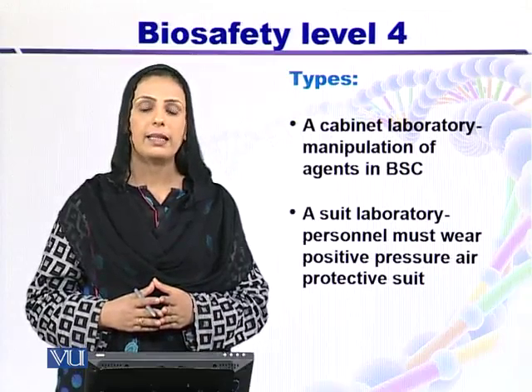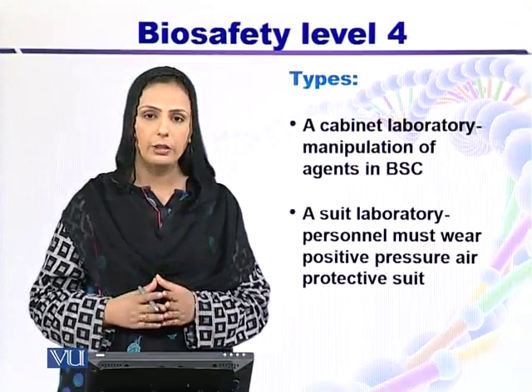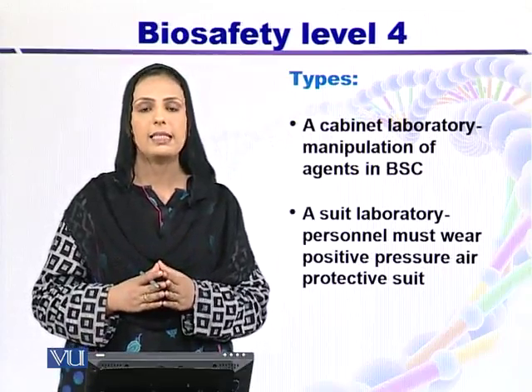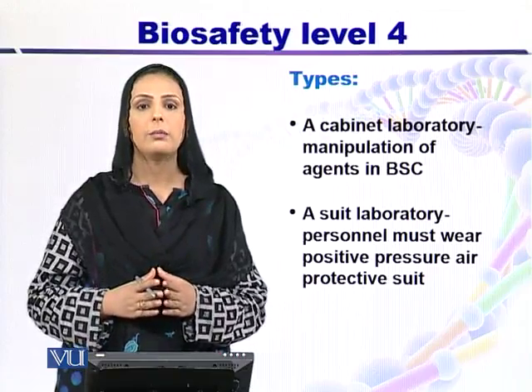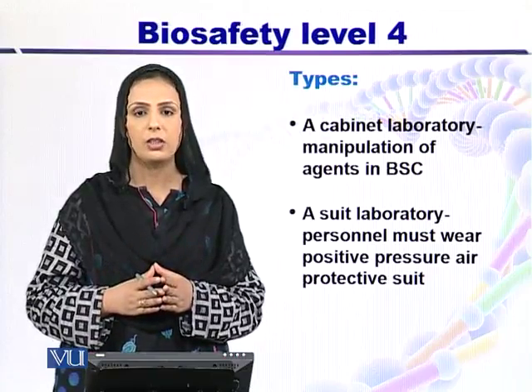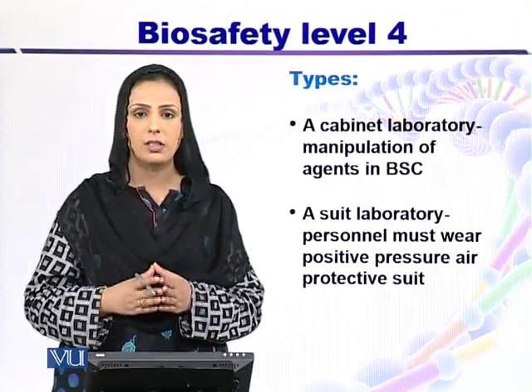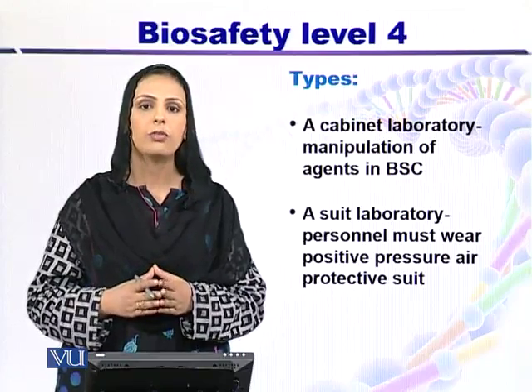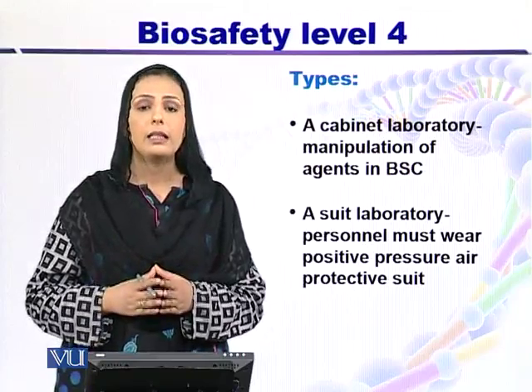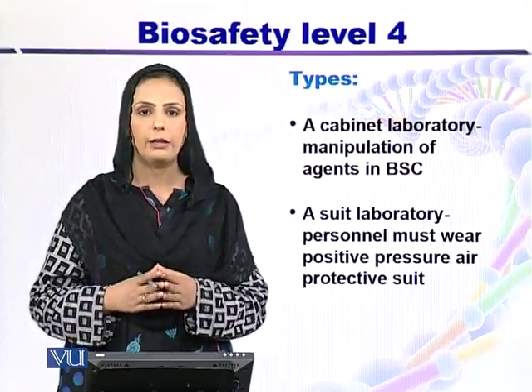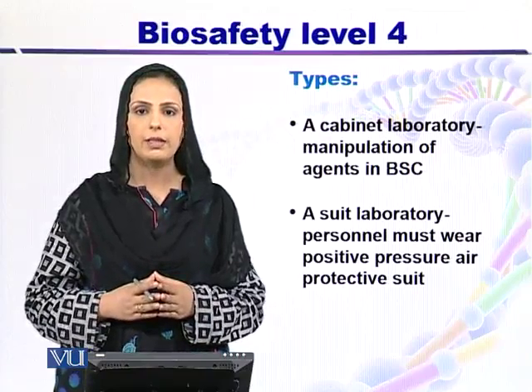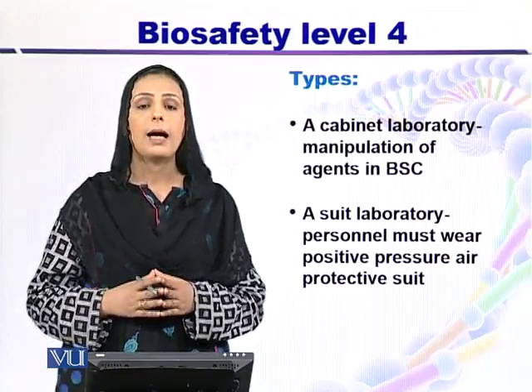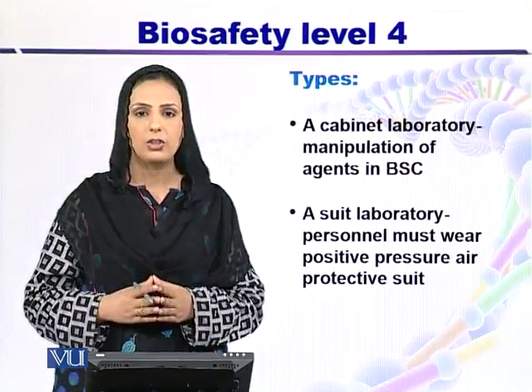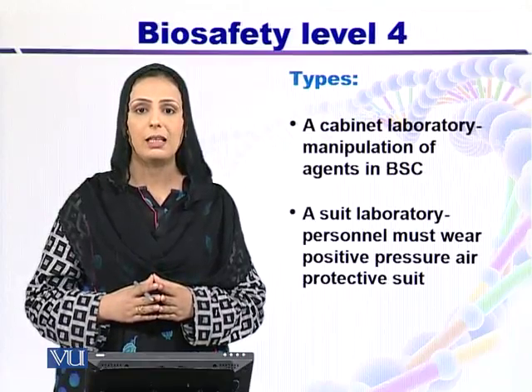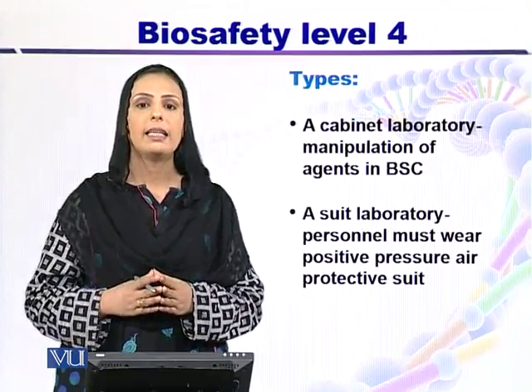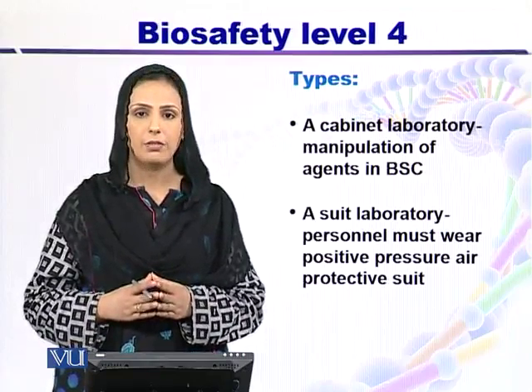Now a biosafety cabinet that is certified and is used according to the manufacturer's details has double doors, and the material that contains infectious agent first passes through the autoclave for sterilization and then it is disposed of from the biosafety cabinet. In the autoclave, sterilization occurs at 121 degrees centigrade for 15 to 20 minutes and the pressure is 15 pounds. The biosafety cabinet must be designed in such a way that if infectious material cannot be sterilized by autoclaving, then it must be removed carefully from the biosafety cabinet.